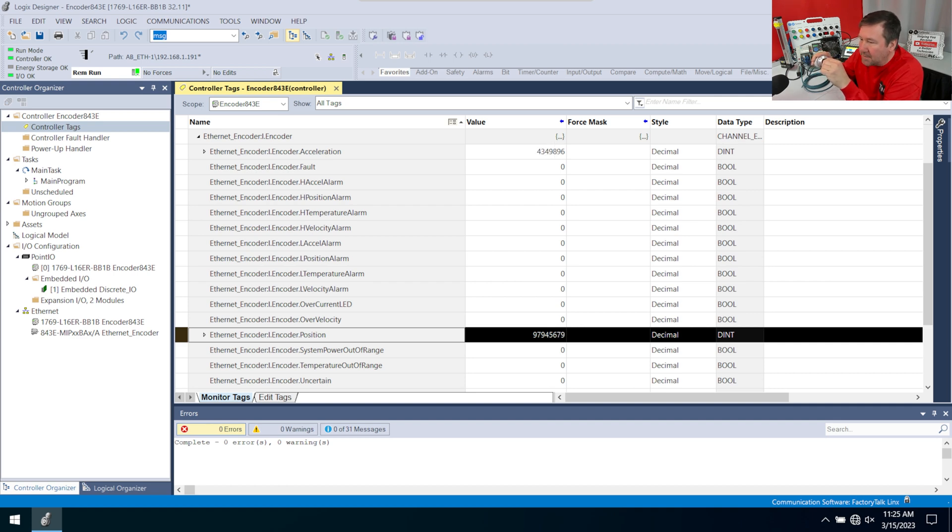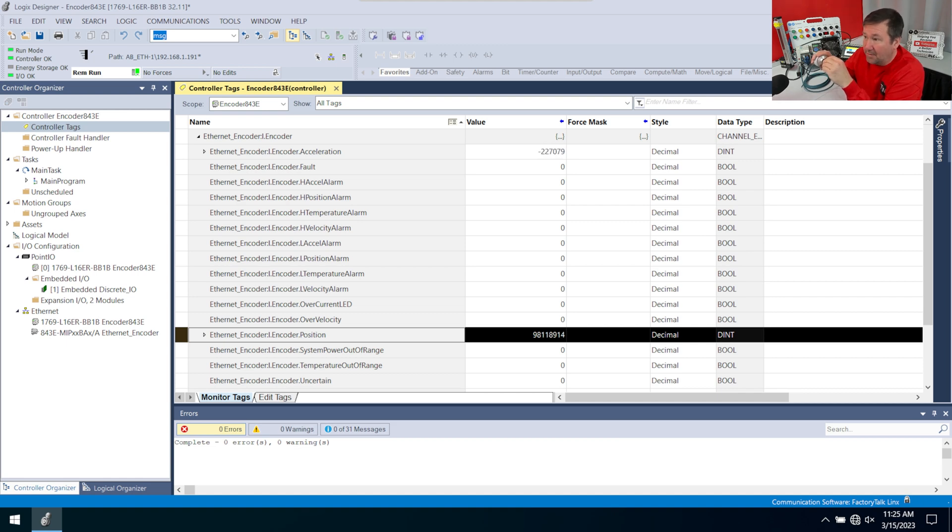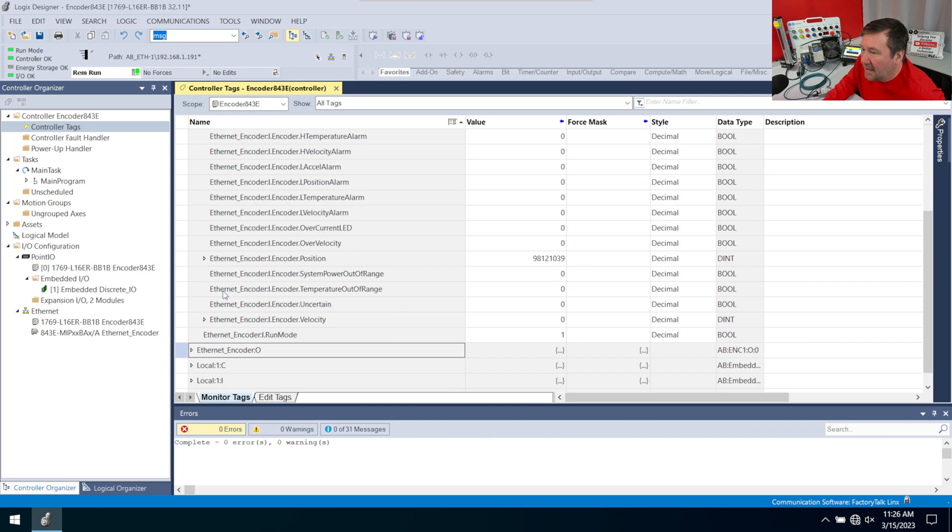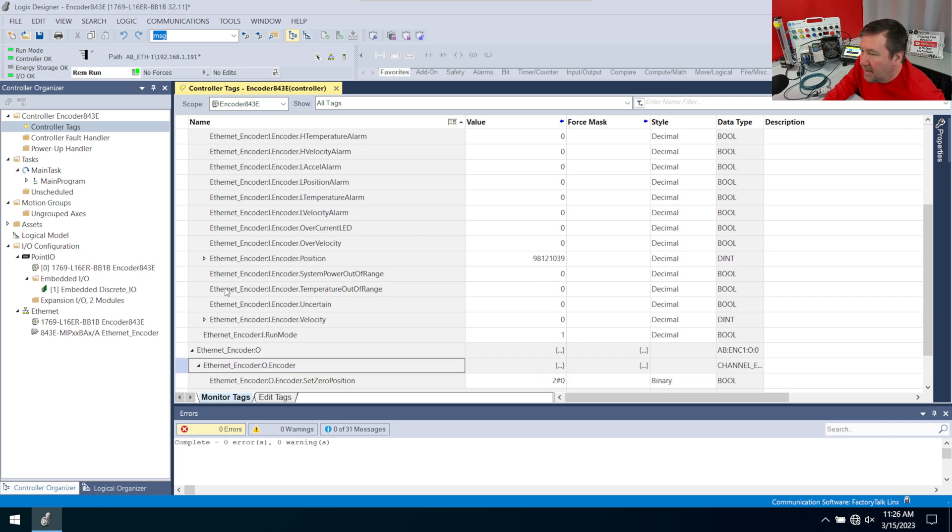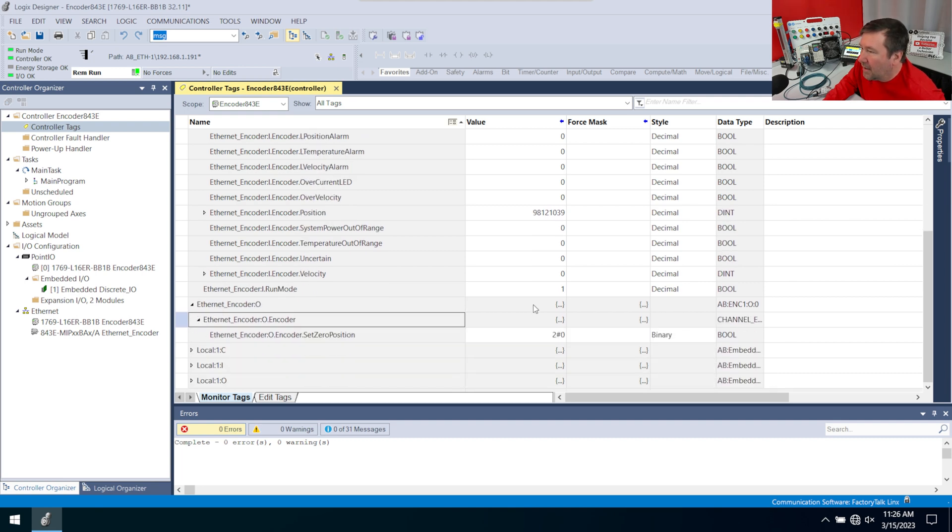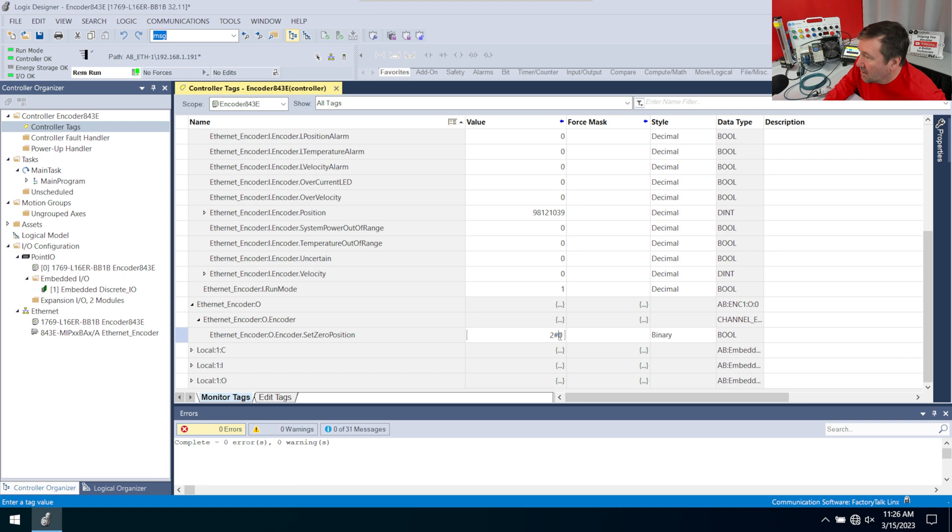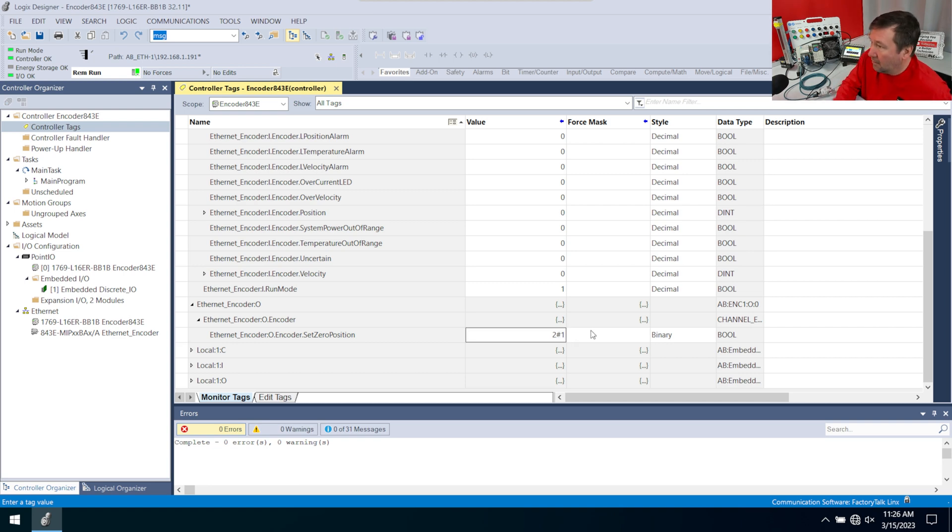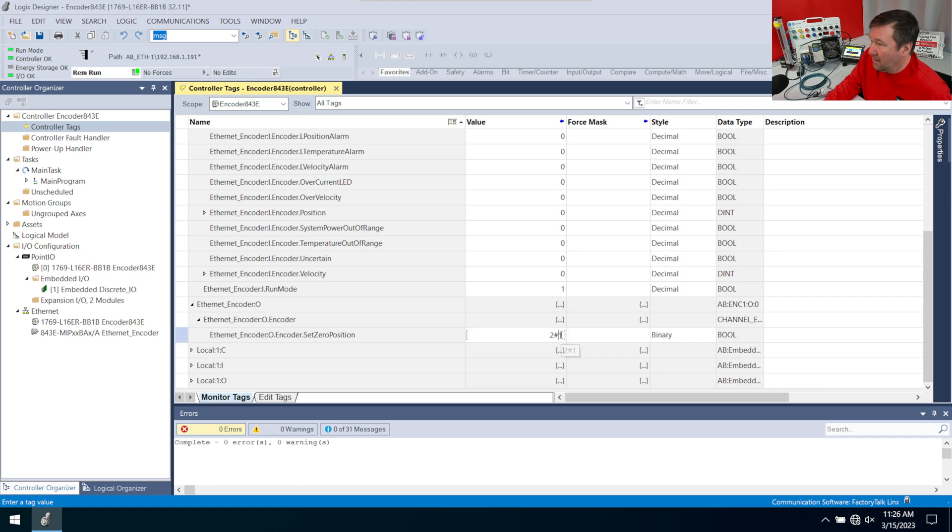Now this is an absolute multi-turn encoder. So we will need to set its reference eventually. And we're going to do that in the Ethernet encoder colon O. So if I open it up, we have zero position. And if we put a one here, that's going to zero this position. So I'm just going to put a one right there. And right away, you see our position went to zero. And we can just put that back as zero.